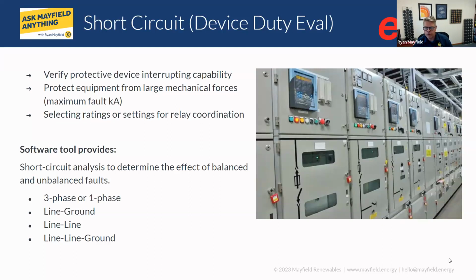Dwelling units, nope. If it's not a dwelling unit, you're doing these per those code requirements. Do you know that, Victor? Yeah, anything outside of residential. Residential is usually handled by your local utility or muni. However, anytime you're doing any type of commercial, industrial, renewable type of site, like a PV farm, that is definitely a requirement, because you want to make sure that in the event of a fault, right, the equipment will be protected.